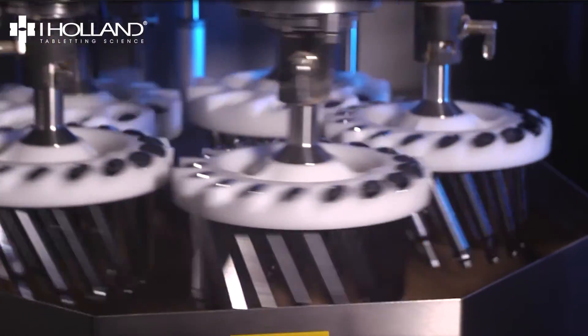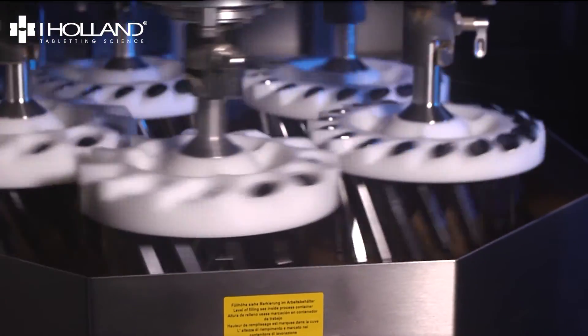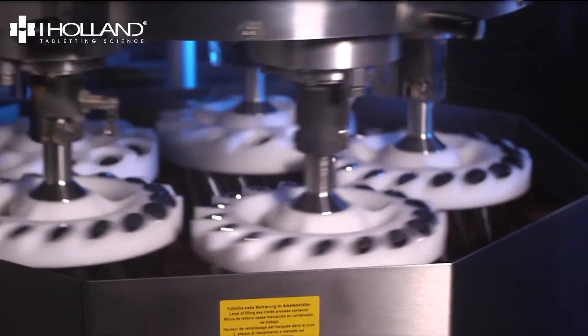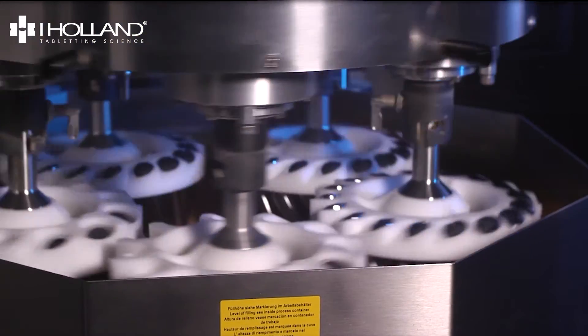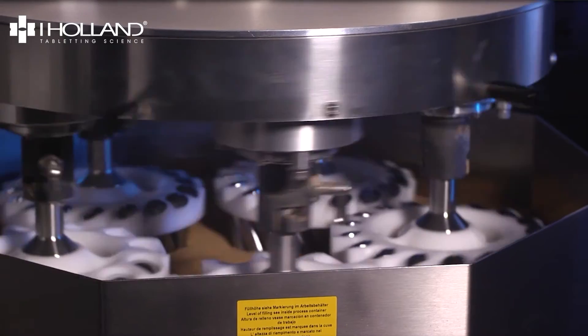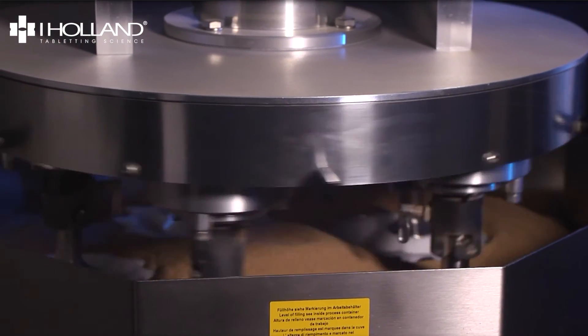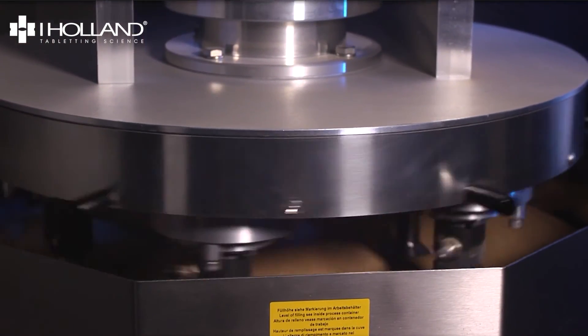MF polishers have a safety interlock fitted to ensure the door cannot be opened while the machine is in operation. Because the machine is in automatic mode, the carriers start rotating at a slow speed whilst lowering down into the media. When the tools are fully submerged, the machine will speed up to the full 45 RPM.